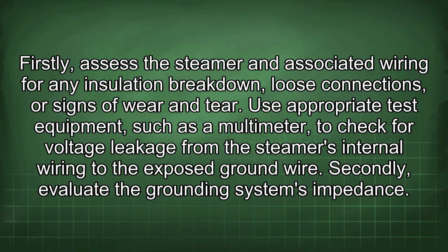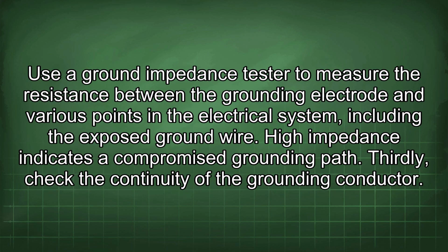Firstly, assess the steamer and associated wiring for any insulation breakdown, loose connections, or signs of wear and tear. Use appropriate test equipment, such as a multimeter, to check for voltage leakage from the steamer's internal wiring to the exposed ground wire. Secondly, evaluate the grounding system's impedance. Use a ground impedance tester to measure the resistance between the grounding electrode and various points in the electrical system, including the exposed ground wire. High impedance indicates a compromised grounding path.